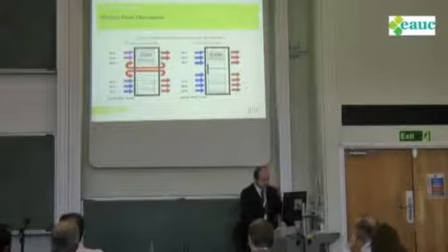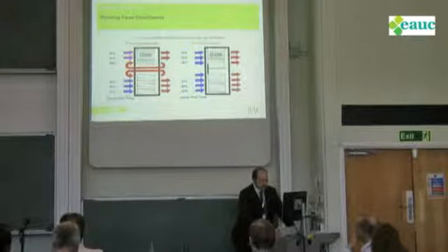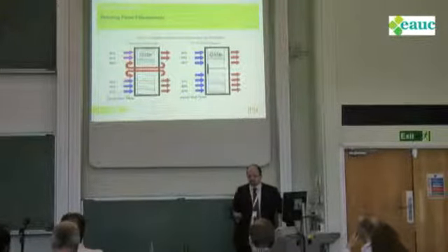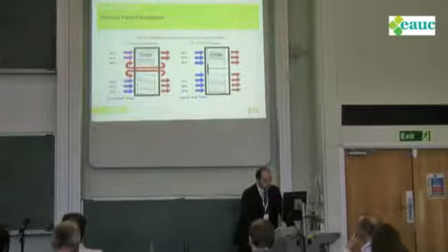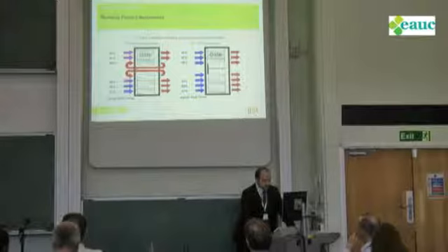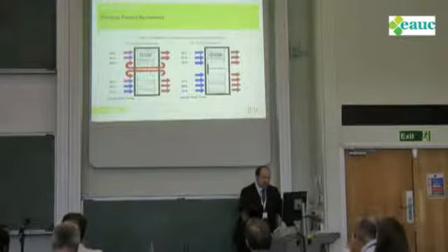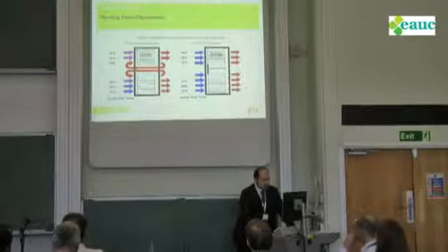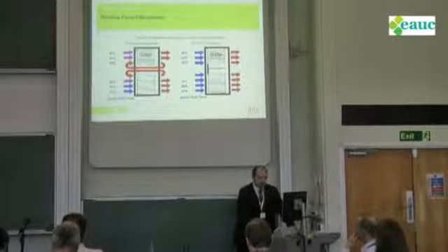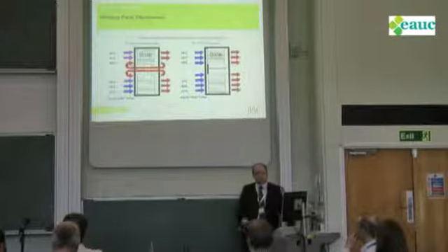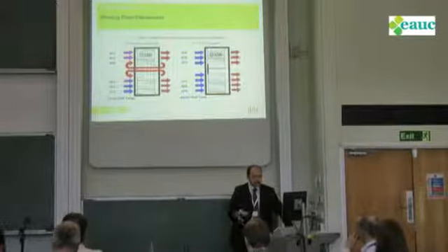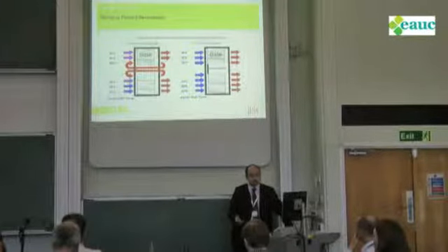If you haven't got blanking panels, the cold air is coming up from the floor. It comes up at 21 degrees, which is quite cold. But you can see that as you go up the rack, because of the mixing of the hot air that's coming back through the other side of the rack, it's starting to heat up. We've got these hot spots near the top of the rack. Very inefficient, very ineffective, and likely to cause some of your servers to shut down if you start to have failures.